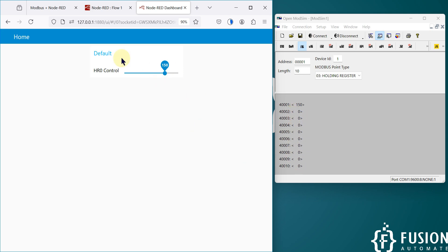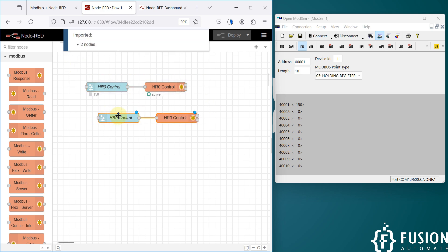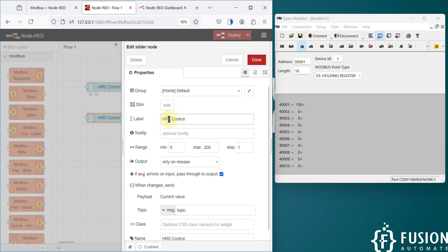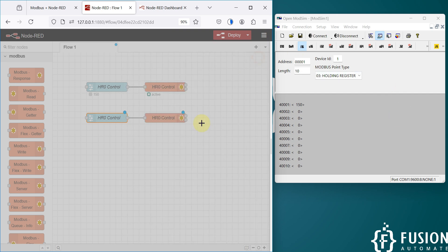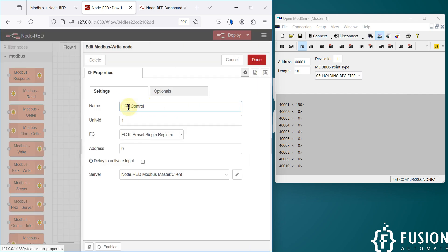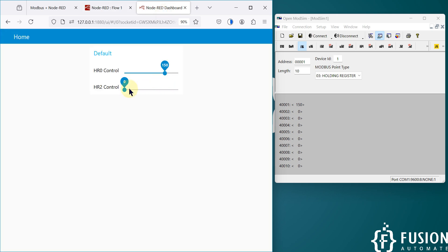Now, the same way, if you want to control any other holding register, just copy and paste the nodes and change the holding register number. Suppose you want to control holding register 2 — that is the third holding register since indexing starts from 0. Set the address to 2 and the maximum value to 100. Rename it HR2 Control. HR2 equals address 2, which is the third holding register.